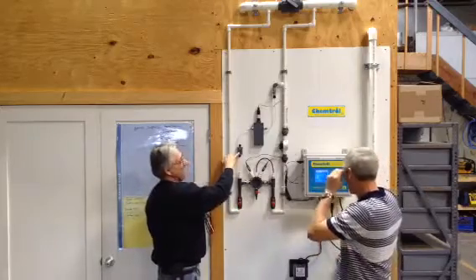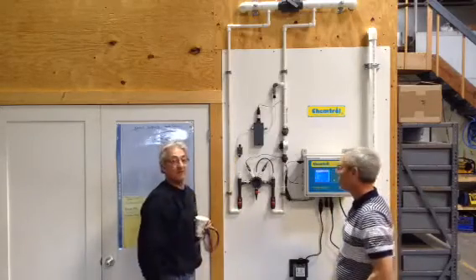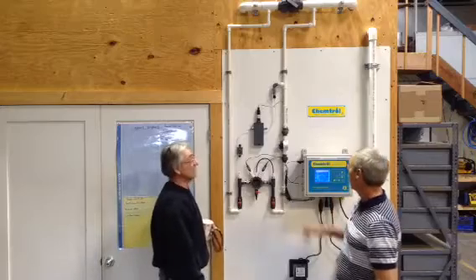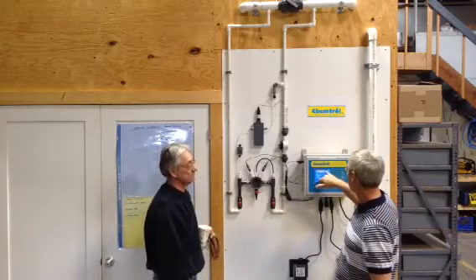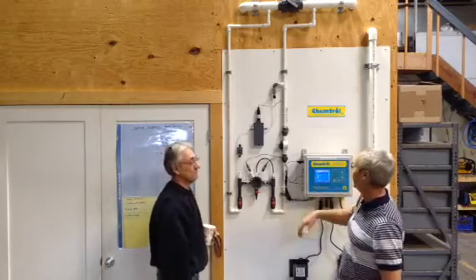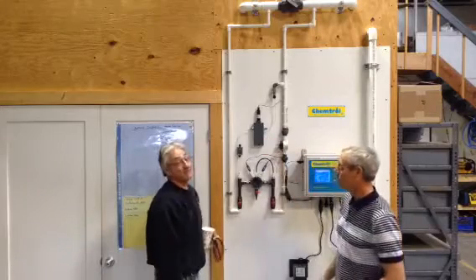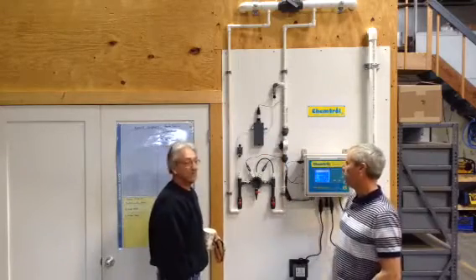And the flow meter only has to be halfway up, so it's got a very small amount of water going through it. But see, it's kind of interesting because we've got like 770 millivolts with a 2.9 reading, so these things are pretty accurate. They're within about a tenth. Really? One way or the other, yeah.